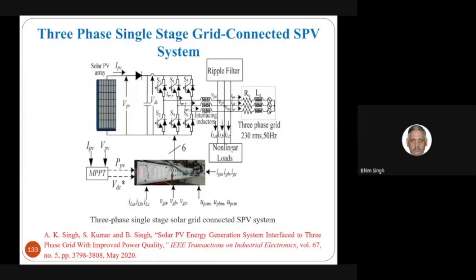Then we come to a similar three-phase system, a three-phase single-stage system. Here the inverter is used not only to convey the MPPT solar power to the grid, but it also meets the requirement of the non-linear local load, so that the grid currents are balanced and at unity power factor, because all kinds of non-linear load can be supplied in this system also.